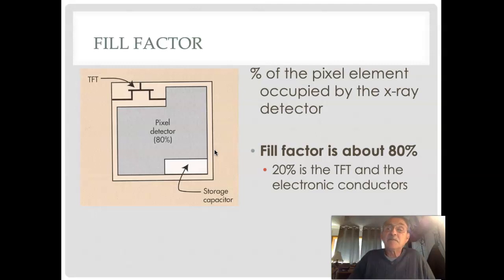The percentage of the pixel element occupied by the X-ray detector is the fill factor. And you can imagine that different manufacturers manufacture them a little bit differently.